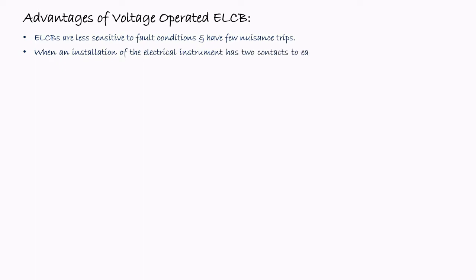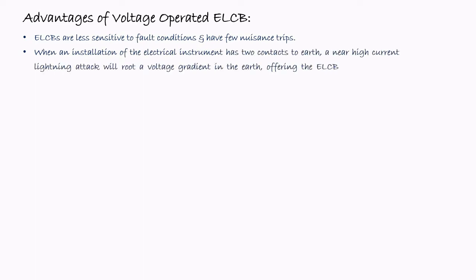The advantages of the voltage operated ELCB. These are less sensitive to fault conditions and have few nuisance trips. When an installation of the electrical instrument has two contacts to earth, a near high current lightning attack will route a voltage gradient in the earth, offering the ELCB sense coil sufficient voltage to cause a trip.